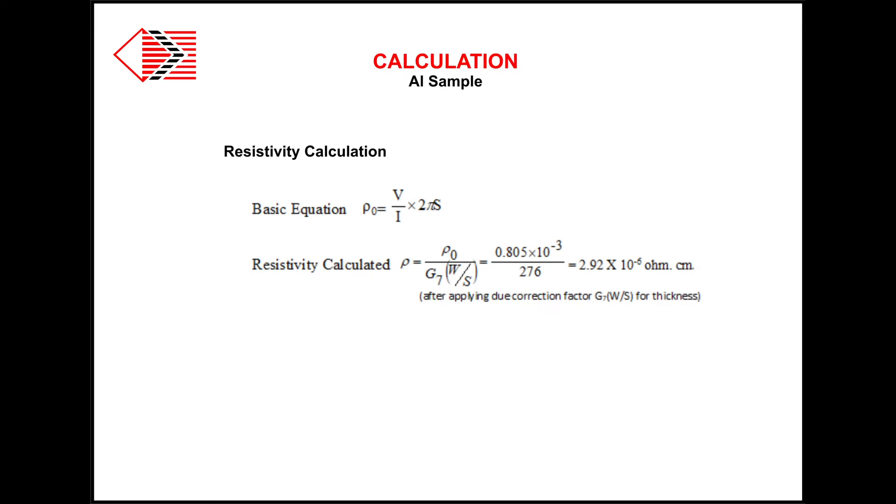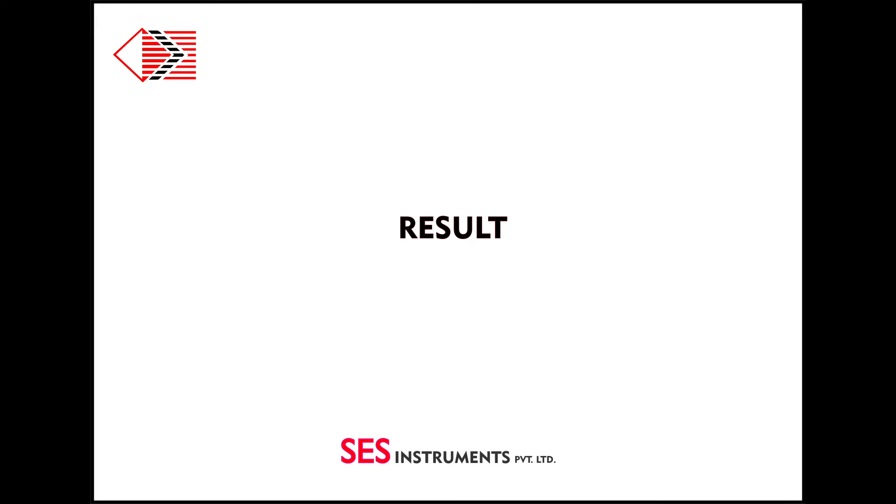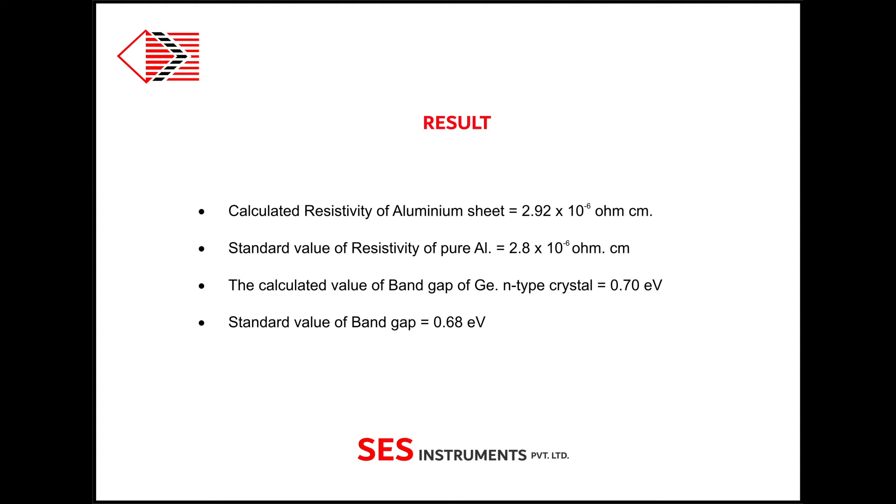This is the equation used for resistivity calculation. For details about the derivation of this equation, you may refer to user's manual equation number 3. Since the thickness of the crystal is very small compared to probe distance, a correction factor G7 for non-conducting bottom surface will need to be applied to get correct resistivity. Again, the details can be studied in user's manual. After calculation, we get the value of resistivity and band gap of aluminum sample and germanium N-type crystal.